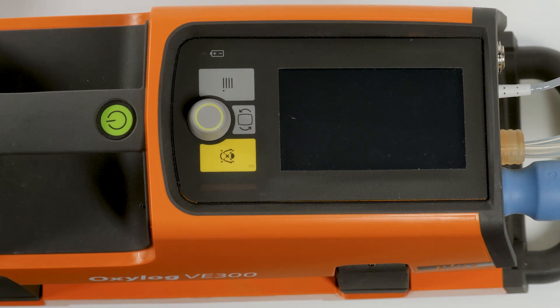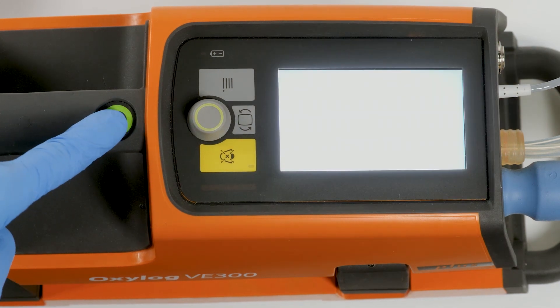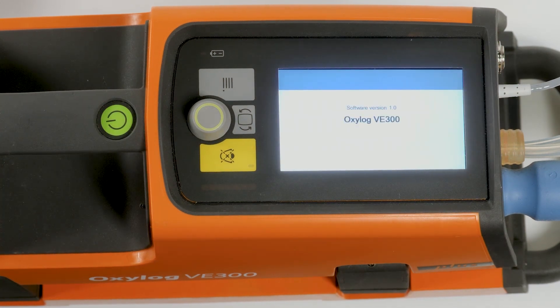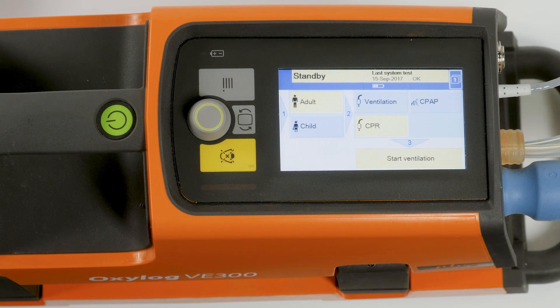To switch the device on, briefly press the start/standby key. The device briefly displays the startup screen indicating the device name and the installed software version.